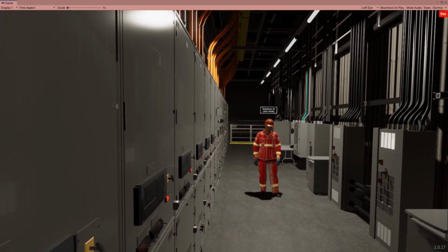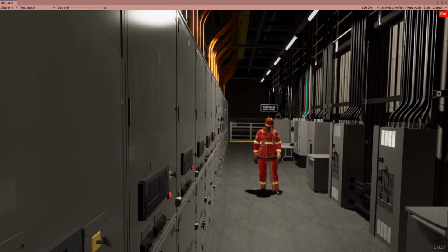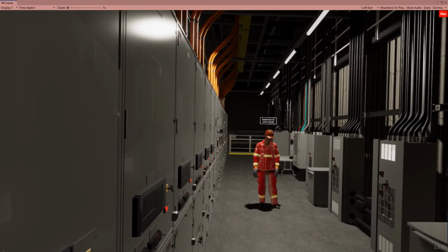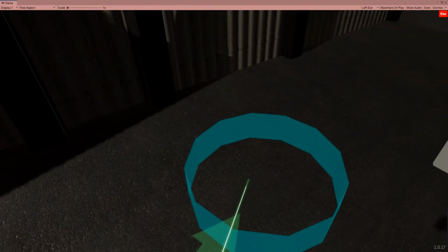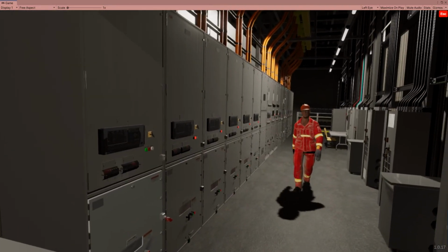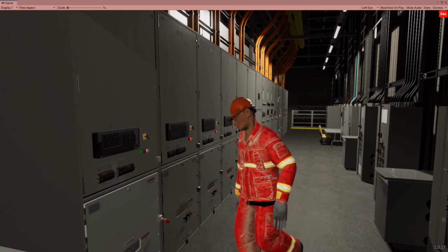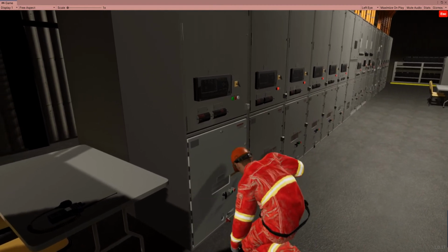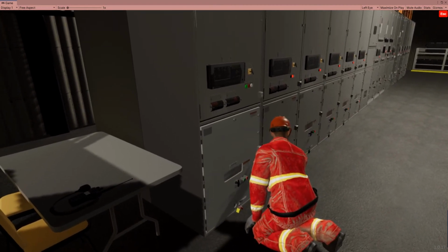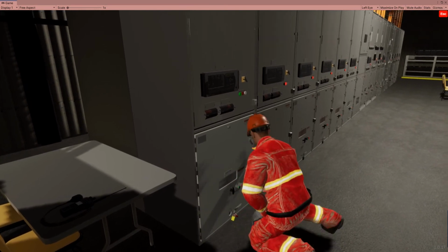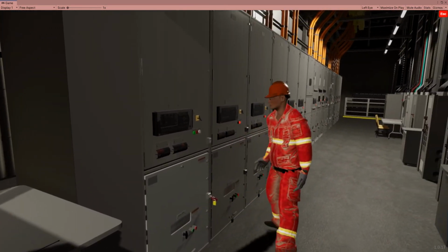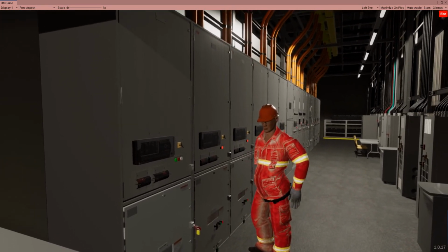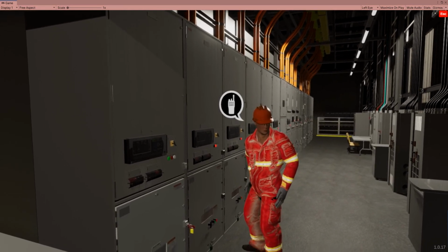Now that your lock is secure, move to the side so that John Smith can visually verify and place a yellow lock on the position release lever and the breaker door. Now that the switching order has been completed, John Smith will inform the issuing authority of completion.